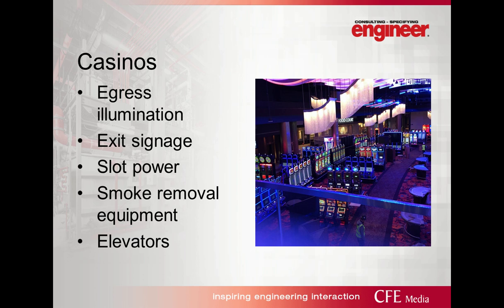Many people, when they hear the word emergency, think that their equipment needs to be on that system. The reality is we're only allowed to have certain things, as mentioned before, on that system by code, because that system is an independently wired system within the building. Egress lighting is one of them. So the IBC defines egress lighting in the case of emergency to be 1 foot candle average measured at the path of egress out of the building.